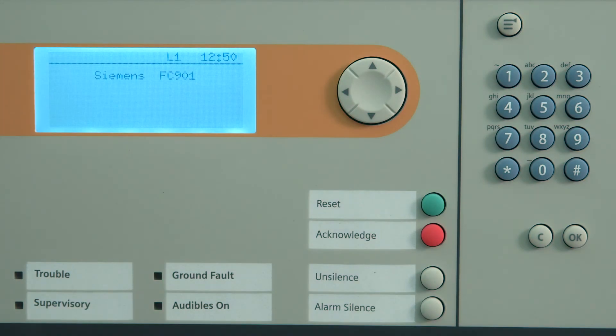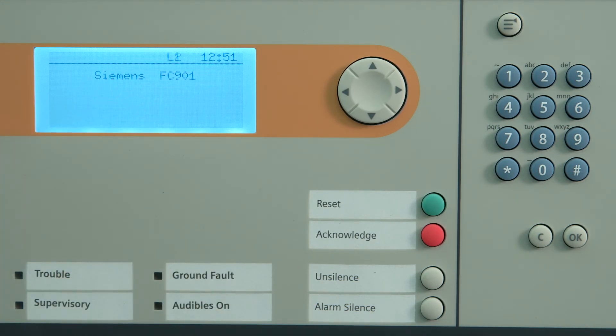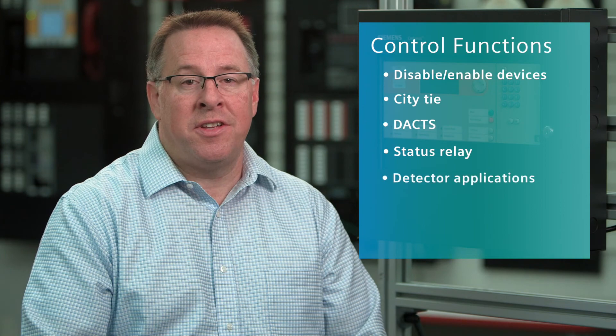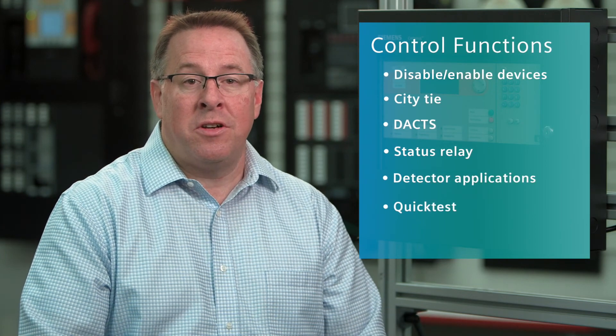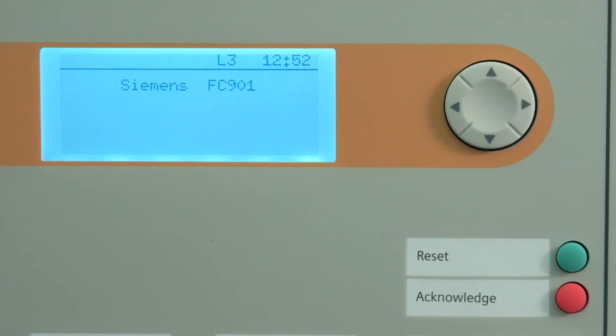The FC901 panel has three access levels. Level 1, shown on the top line in front of the time, is the default user. Level 2, which should be reserved for authorized technical users, provides control functions such as disabling and enabling of devices, city tie, DACTS, status relays, detector applications, quick test, and setting the time and date. Level 3, reserved for authorized technicians, encompasses all Level 2 rights, along with editing device labels and system labels, and changing passwords.